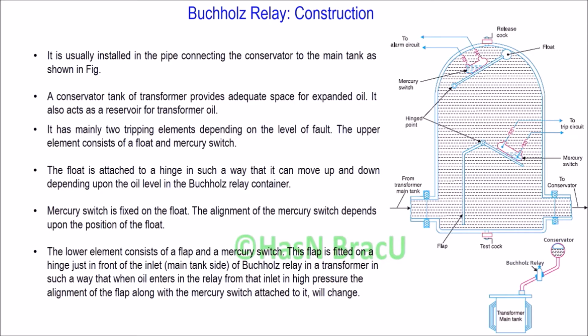In this video, we will discuss the construction and operating principle of Buchholz relay. Here you can see the construction of Buchholz relay. The relay is installed in the pipe connecting the conservator to the main tank. You can see here, this relay is installed between the main tank and conservator.